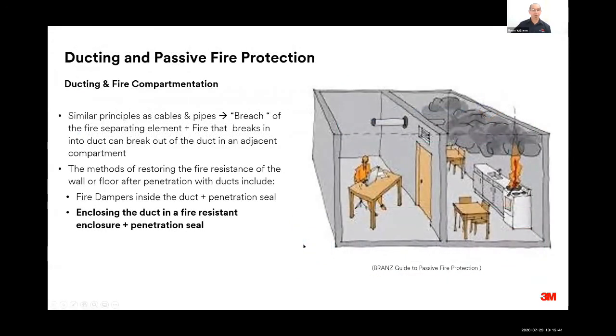So I mentioned that ductwork, in principle, is similar to other penetrations. Once it passes through a wall or a floor, the fire resistance rating of that element is compromised. So we need a method to restore the fire resistance rating. Typically, for most types of ducts, or quite a range of ducts, the method of restoring the fire resistance is through fire dampers that are installed inside the duct at the junction where the duct penetrates the separating element. But an alternative method is through enclosing the duct with a fire-resistant enclosing construction, and also dealing with the gaps around that as well.